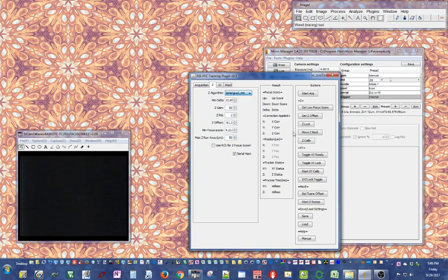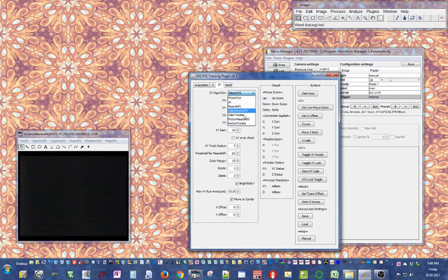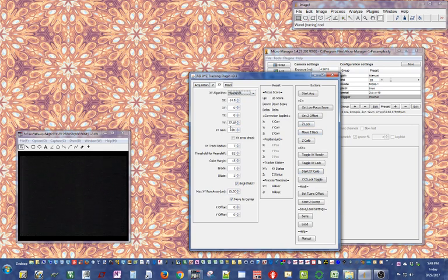Unlike Z, where changing the Z focusing algorithm requires running Z calibration again, with XY you can change algorithms without re-running calibration. The XY stage calibration is only needed if you change objectives (since that changes magnification and affects XY gain), or if you change the camera, the stage, put the camera on a different photo port, or rotate the camera to a different orientation. Whenever you think the orientation between camera and stage has changed, run XY calibration — it only takes a few seconds, so when in doubt, run it again.